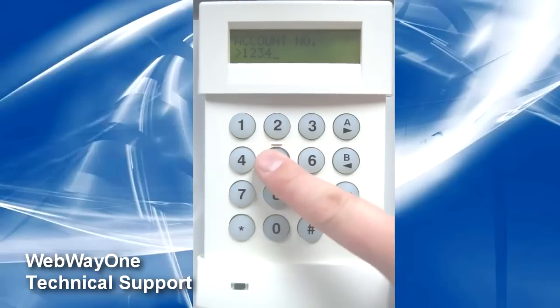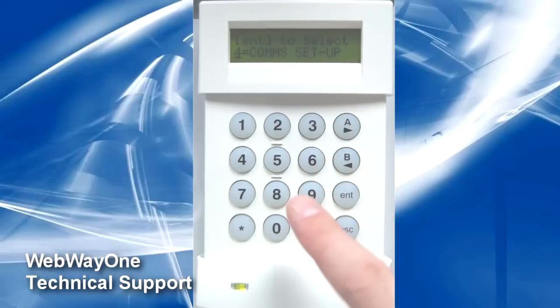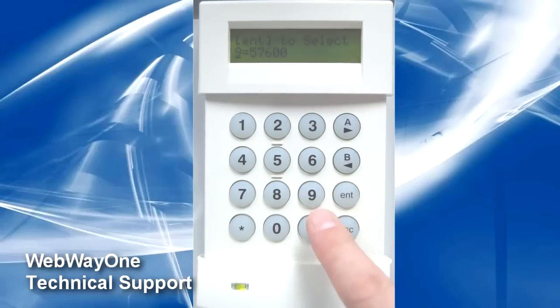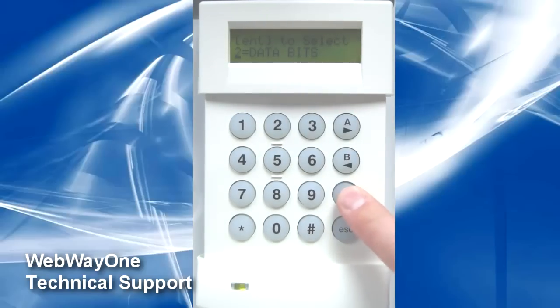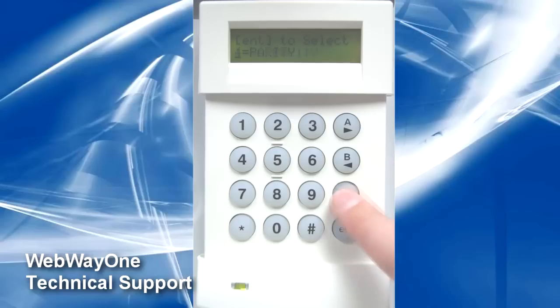Once the account number is set, go back and enter into option 4 for the comms set-up. In here, check the baud rate option is set to 57,600. The data bits option is set to 8 data bits. The stop bits option is set to 1 stop bit. And finally, the parity option is set to no parity.